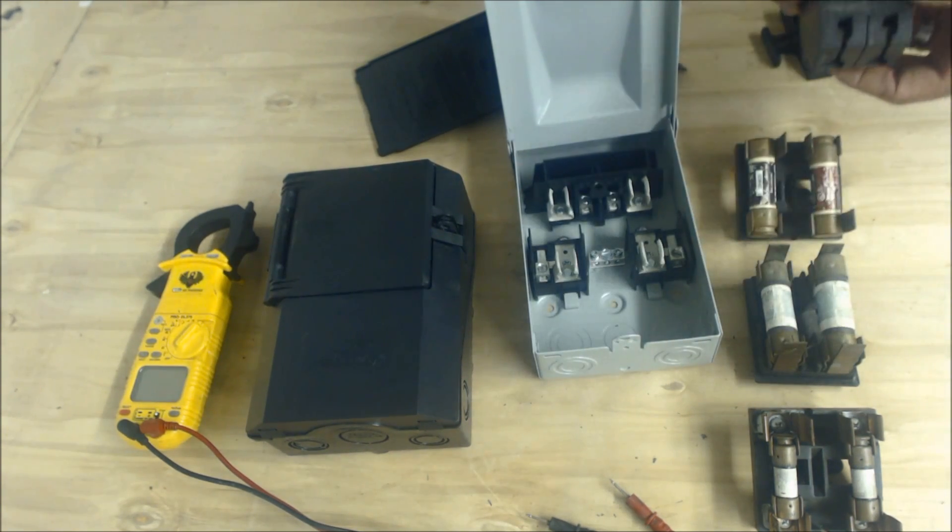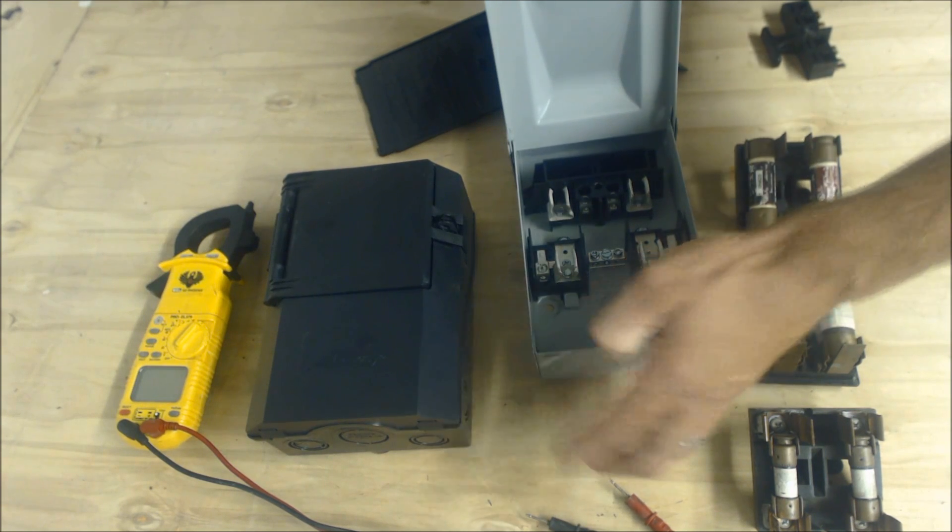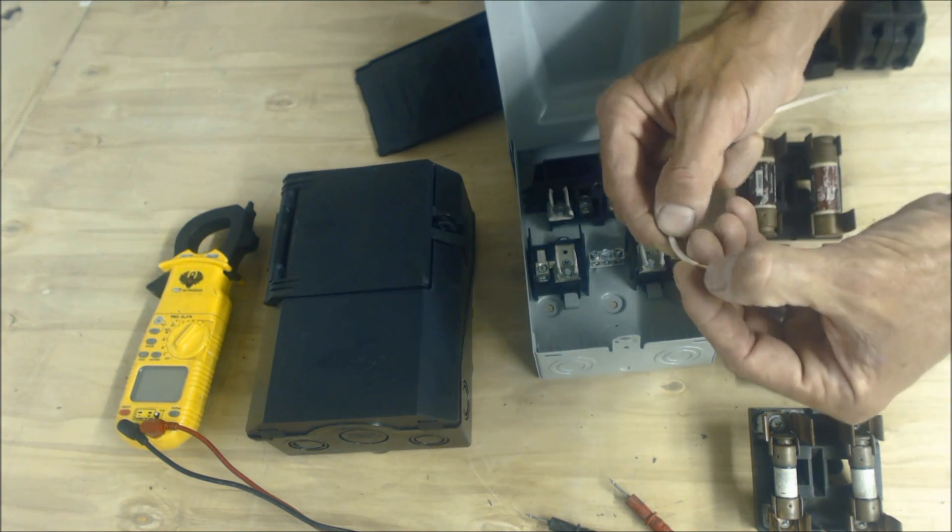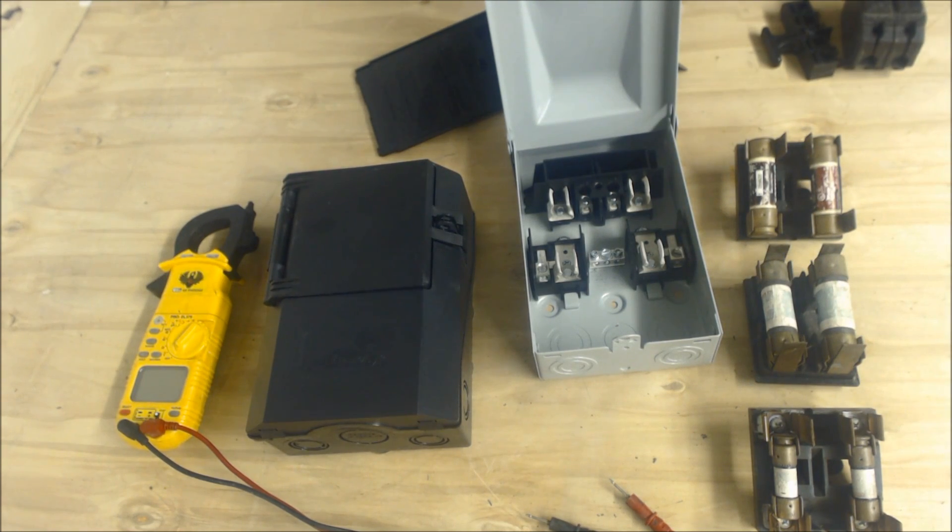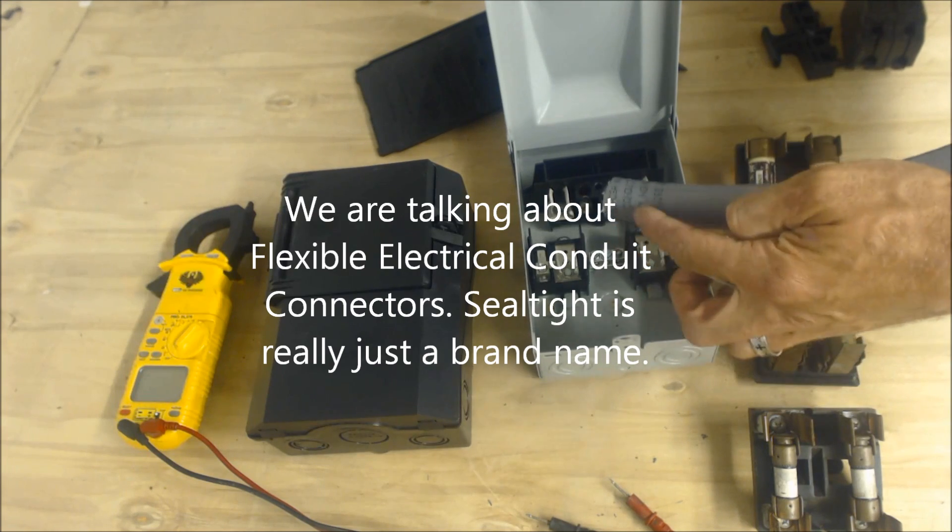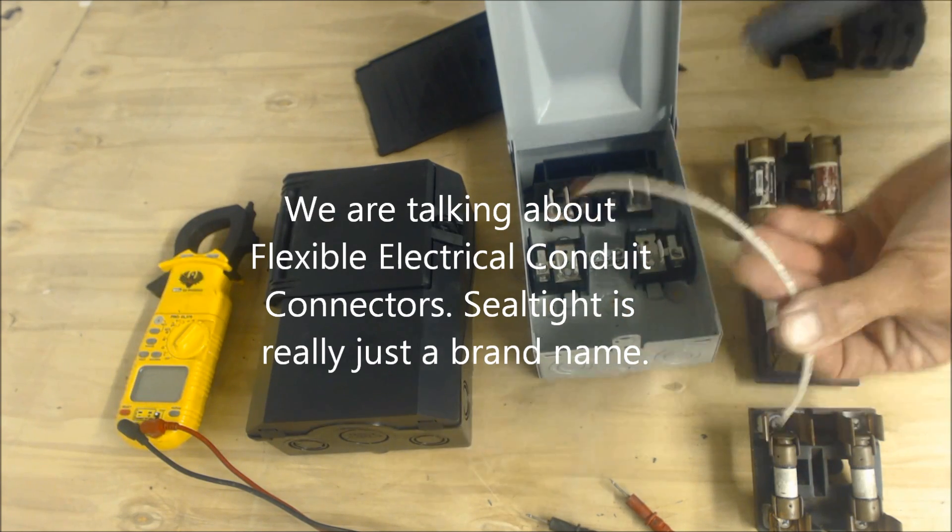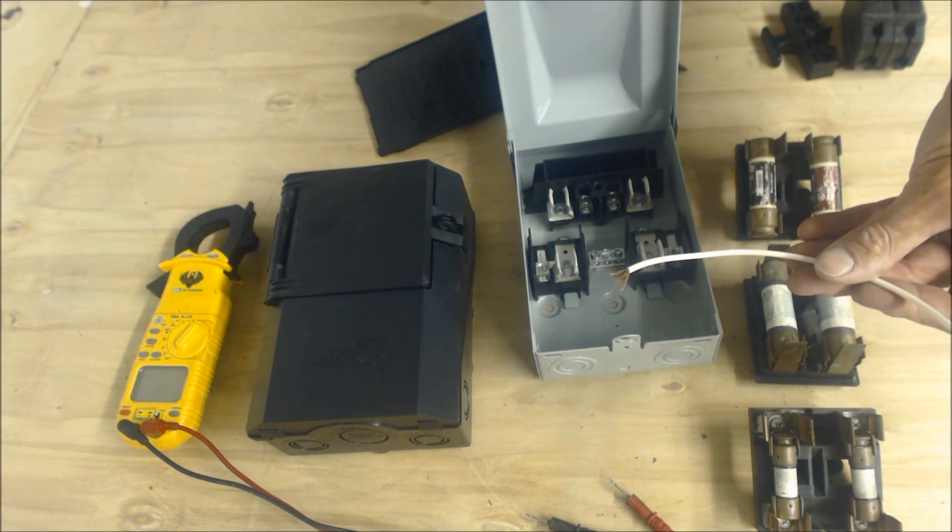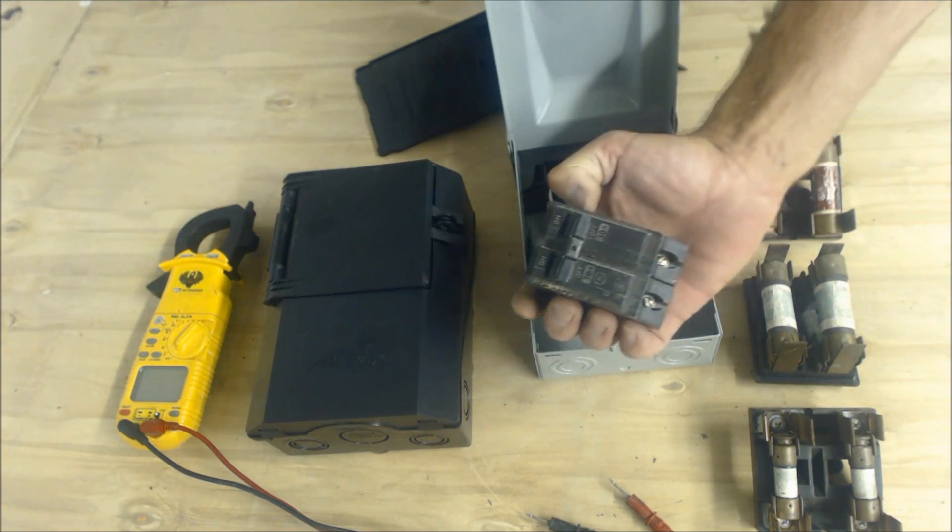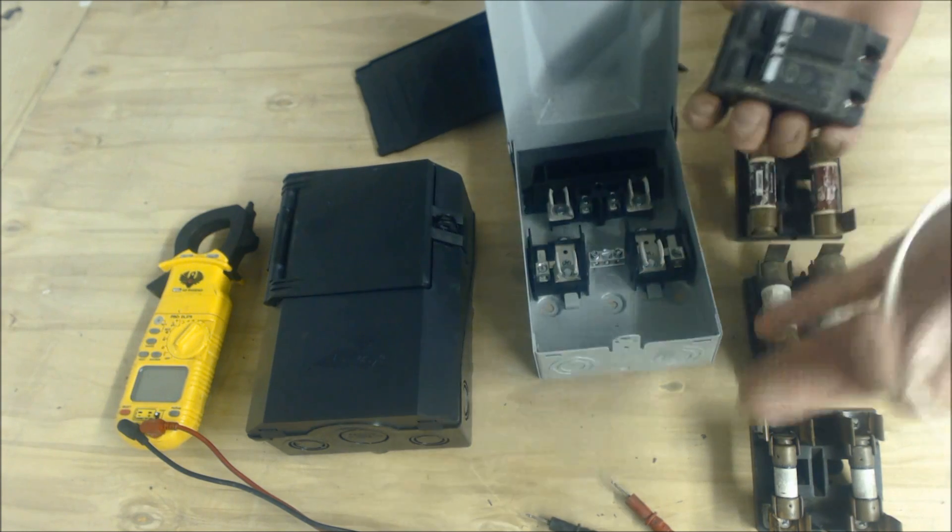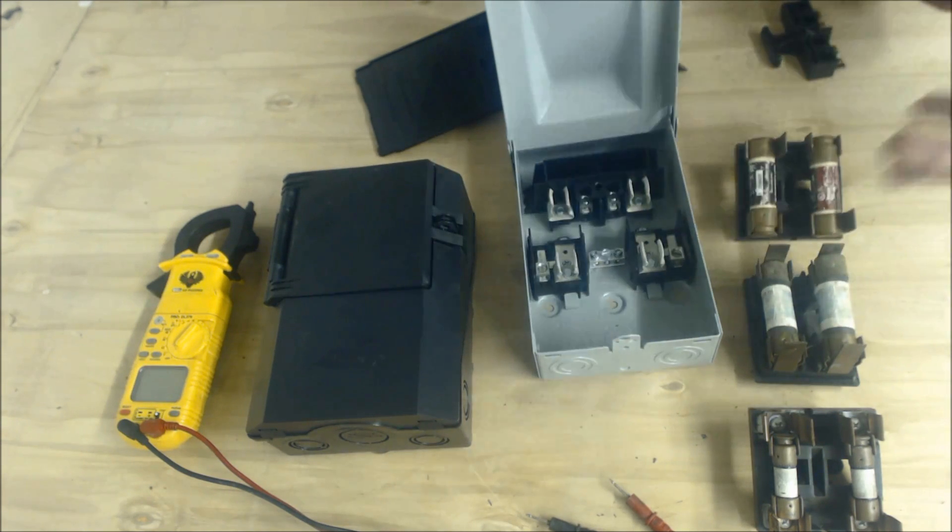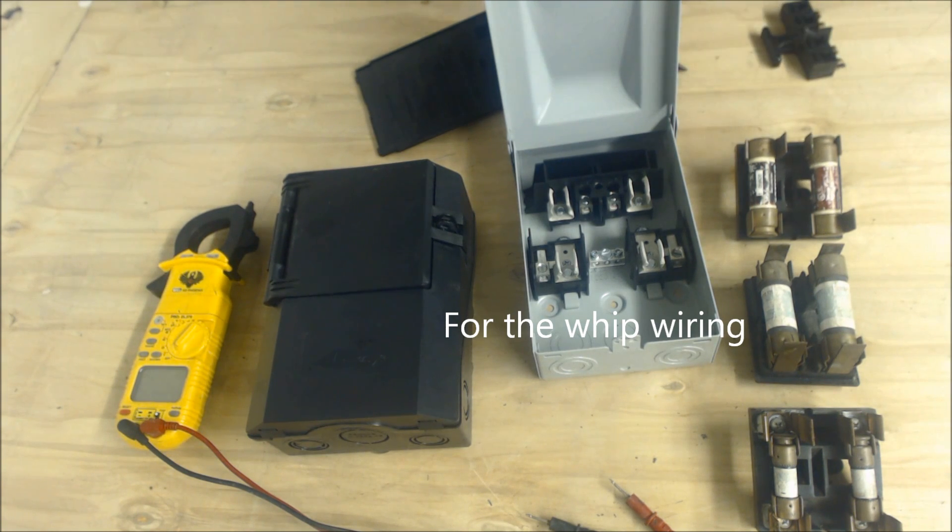So all I can say is you want to make sure that you have the proper wire on your whip. And it needs to be a THHN wire or something like that, stranded, that's rated for that to be in your Sealtight. So in your whip, you want to have your stranded copper being the right size, the right gauge thickness. So for instance, if you were working with 30 amp, then you would use 10 gauge. And if it was 20 amp, you'd use 12 gauge. If it was 15 amp, you'd use 14 gauge, so on and so forth.